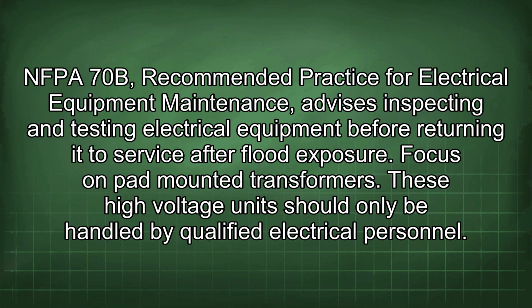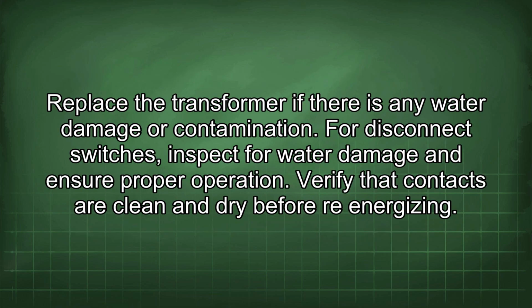NFPA 70B, recommended practice for electrical equipment maintenance, advises inspecting and testing electrical equipment before returning it to service after flood exposure. Focus on pad-mounted transformers. These high-voltage units should only be handled by qualified electrical personnel. Replace the transformer if there is any water damage or contamination. For disconnect switches, inspect for water damage and ensure proper operation. Verify that contacts are clean and dry before re-energizing.